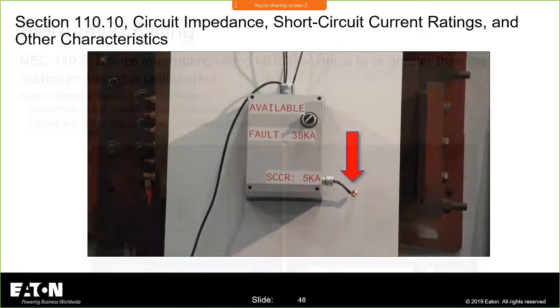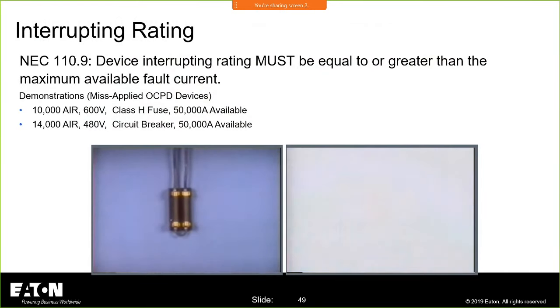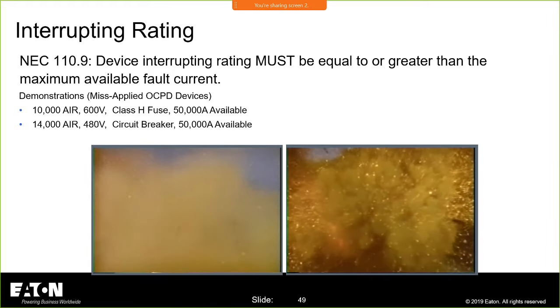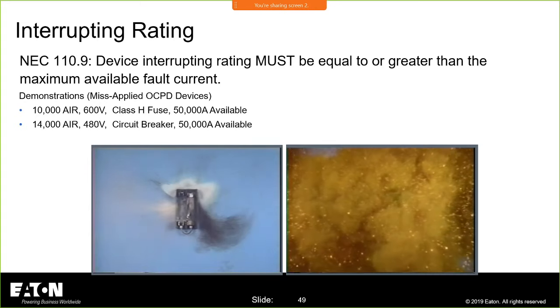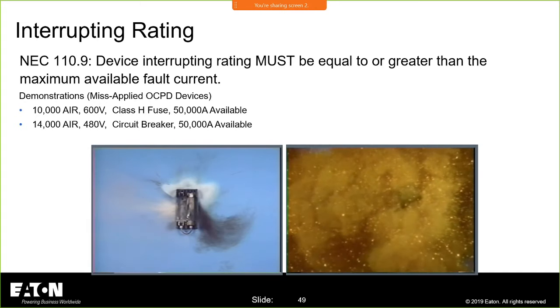So when you misapply a product, whether it's the short circuit current rating or the interrupting rating of an overcurrent protective device, you are going to have an unintended rapid disassembly in the field. You're going to let the smoke out. This is a serious misapplication.